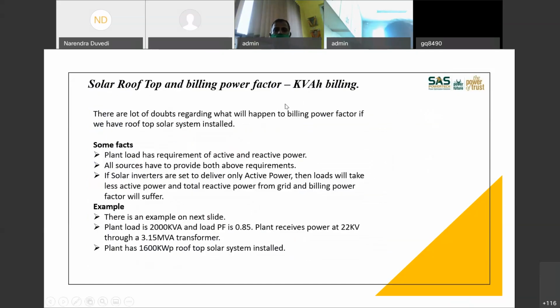Now let us come to an interesting thing. So many of you have rooftop solar installations working with you, and there is always a doubt as to how it will affect my power factor. Now let us understand some facts. Plant load has a requirement of active and reactive power. See, all motors, transformers, cables, whatever you have installed in your factory, they require active as well as reactive power. No transformer will work unless a magnetic field is created. No motor will work unless a magnetic field is created. So reactive power is a requirement of load. Active power is also a requirement of load.